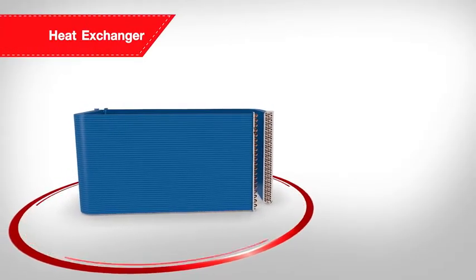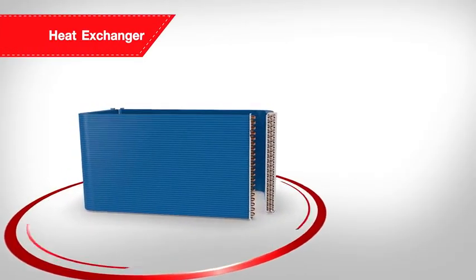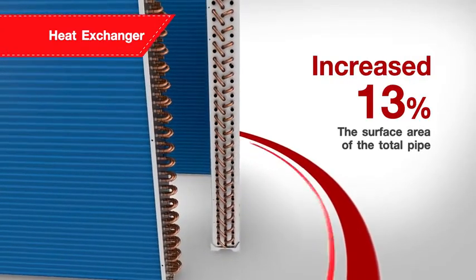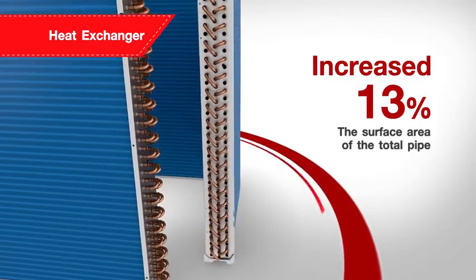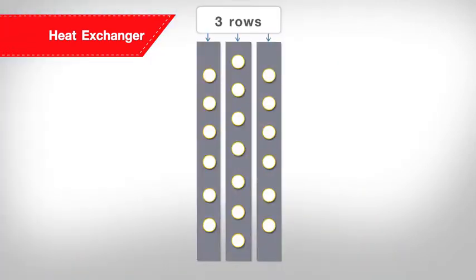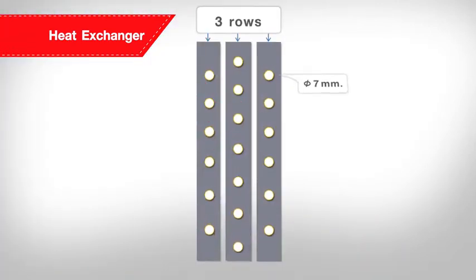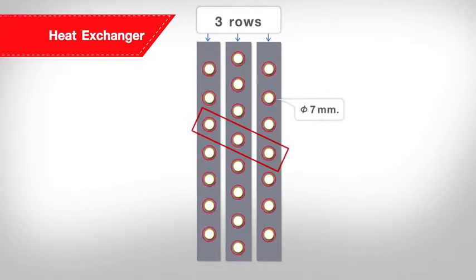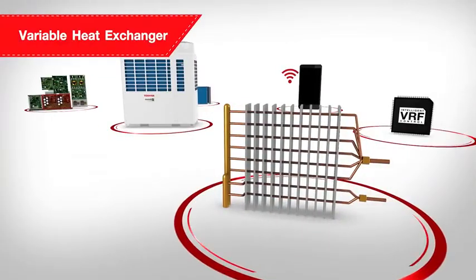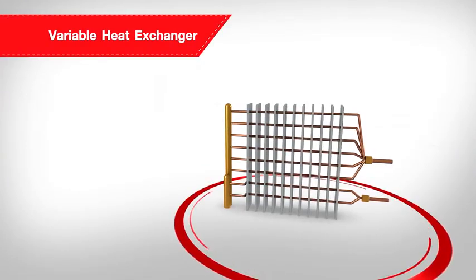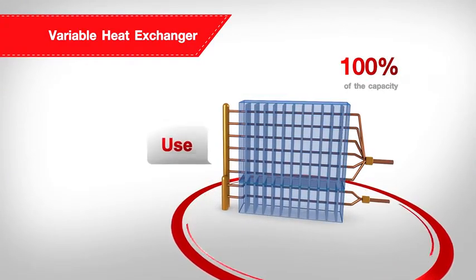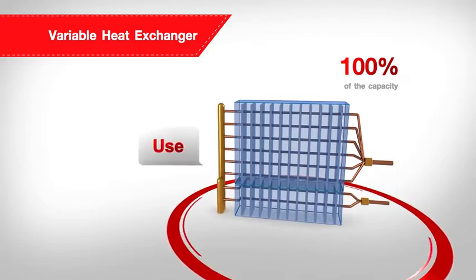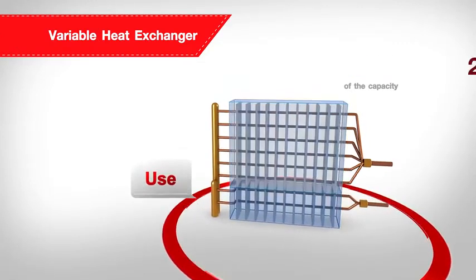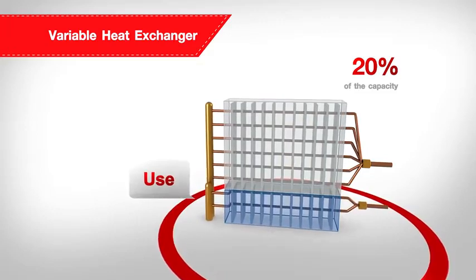The new heat exchanger provides SMMS-e with up to 13% more surface area of the total pipe, and the improved dimension of 7mm new triple layer pipe configuration increases the contact area between the pipe network and the air flowing through the heat exchanger for greater energy efficiency. Additionally, the variable heat exchanger allows the outdoor unit to determine an appropriate heat exchanger performance to suit the required capacity load from 100% to 20% to achieve high energy saving.